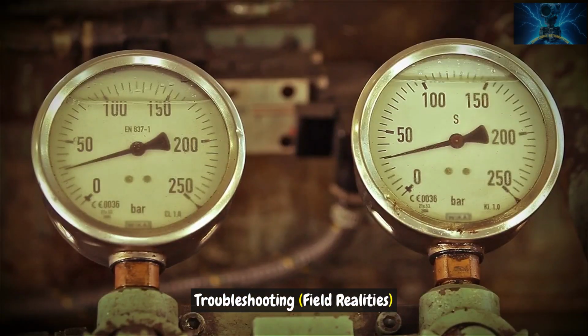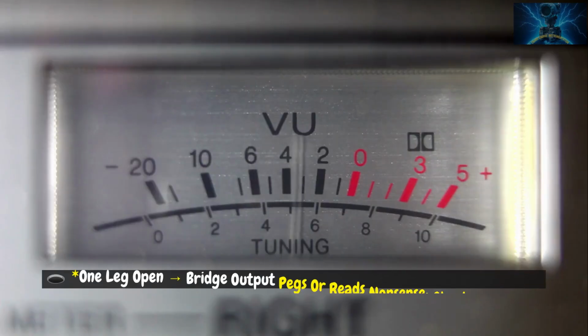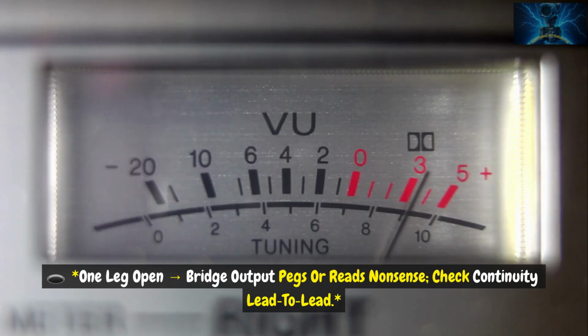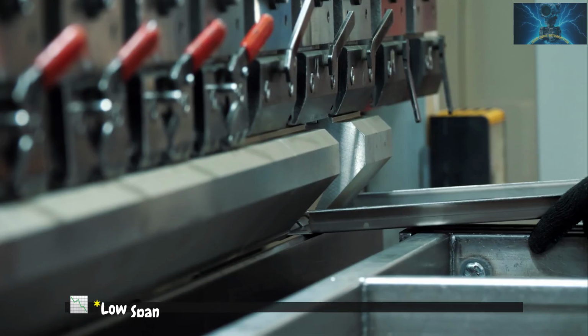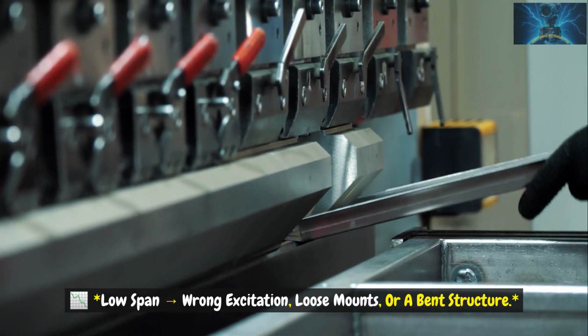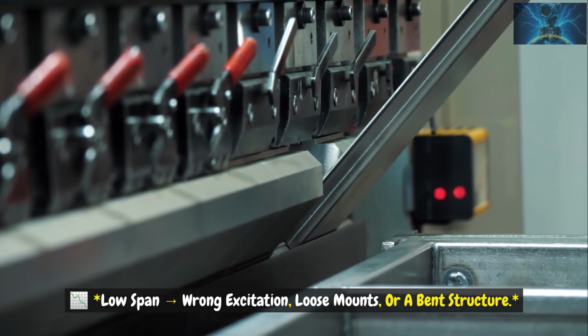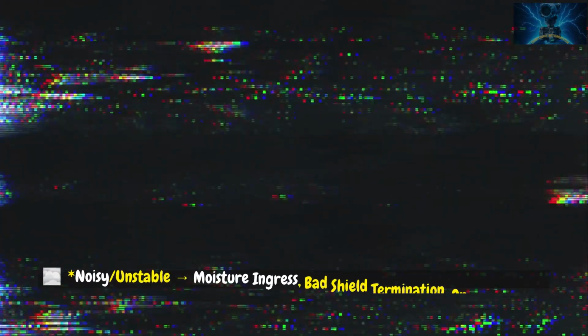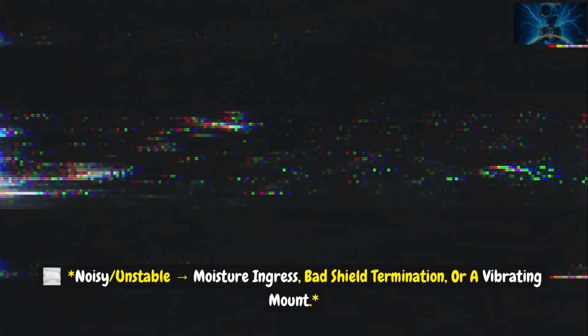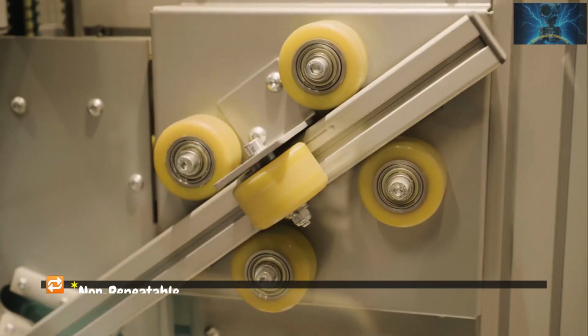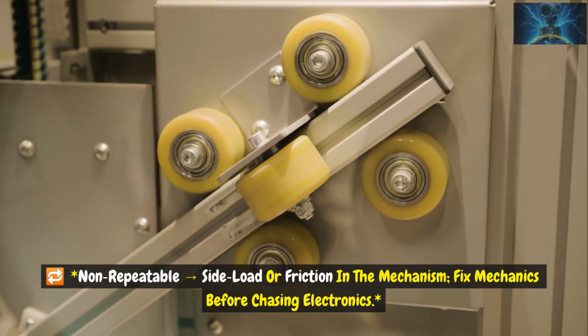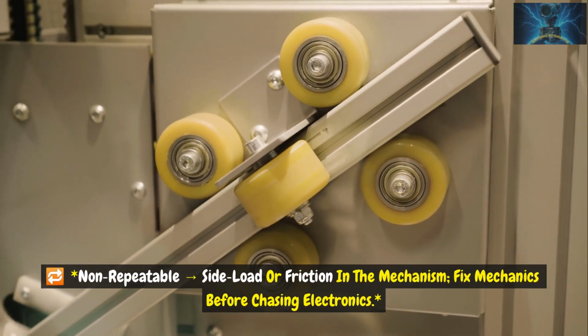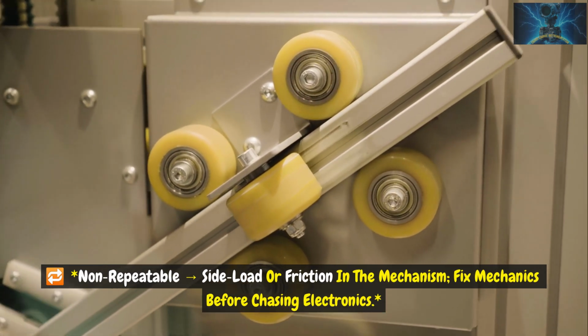Troubleshooting, field realities. If 1 leg is open, bridge output pegs or reads nonsense. Check continuity lead to lead. Low span: wrong excitation, loose mounts, or a bent structure. Noisy, unstable: moisture ingress, bad shield termination, or a vibrating mount. Non-repeatable: side load or friction in the mechanism. Fix mechanics before chasing electronics.